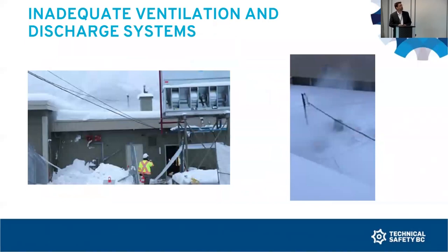So as I mentioned before, we also looked at ventilation systems and discharge systems as part of this event and the role that they played. We did a very simple test, a smoke test, where we ignited a smoke candle. It's a very straightforward thing to do, and it's not expensive. We ignited it within the mechanical room, and we just watched and recorded how the smoke was evacuated from the room and where it went outside of the building.